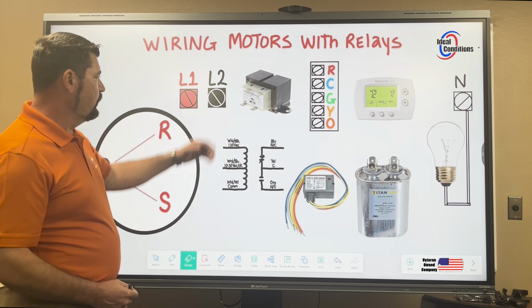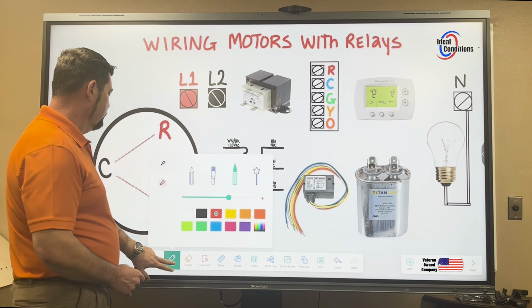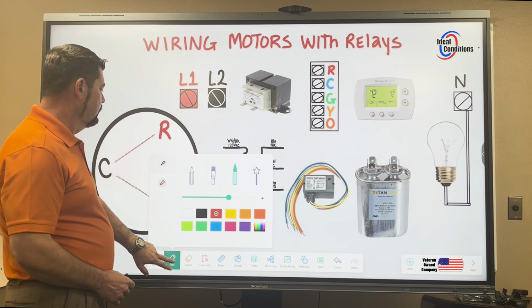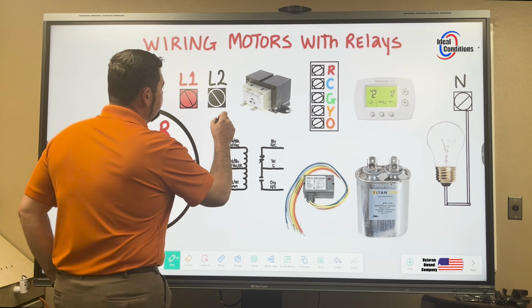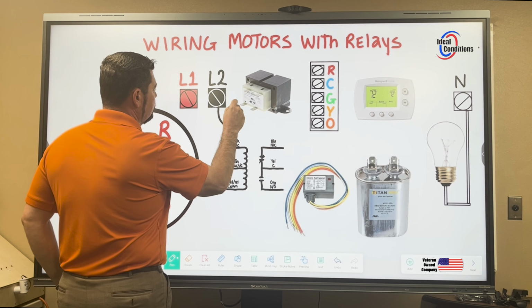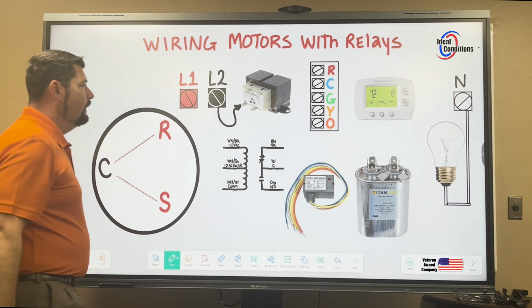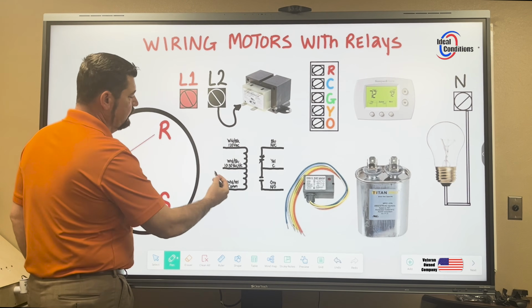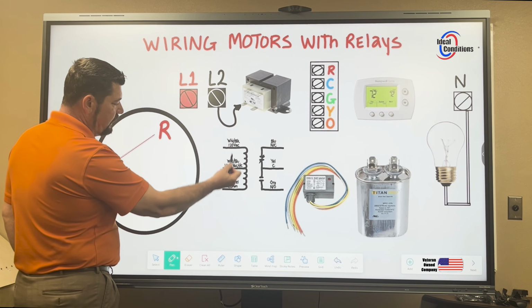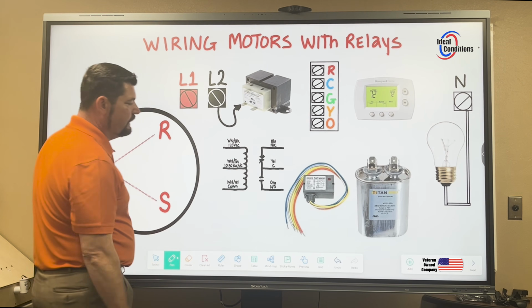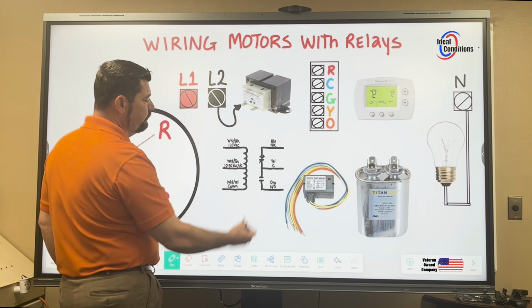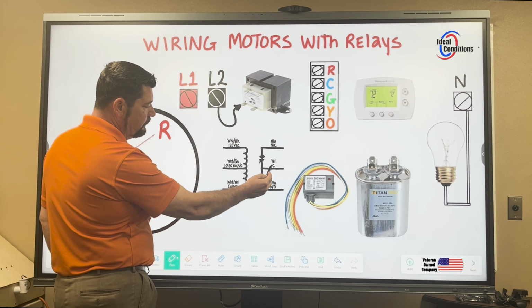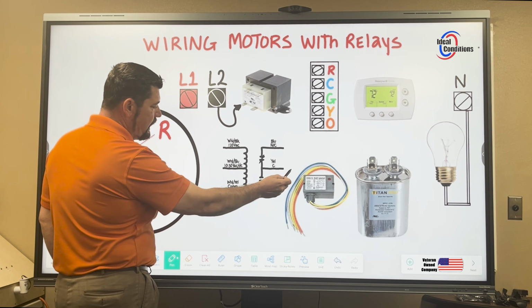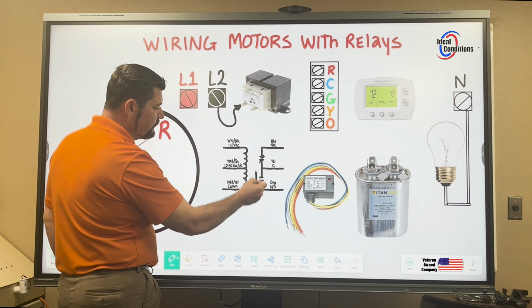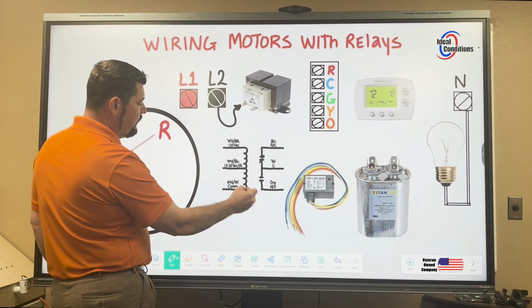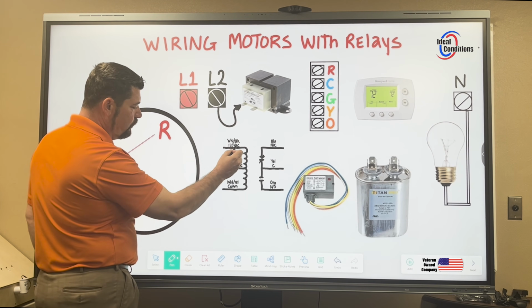Getting right into it, we're going to go with L2 first, and make sure I get my colors right. Yeah, we're good. We're going to wire up one side of the transformer. All right, there's L2, and we're going to come down. And if you look here, one side is my coil voltage, one side is my contact. I have an input and two outputs. This middle one here, the yellow common, is an input. As power comes in, it's going to come out on the normally closed or on the normally open.